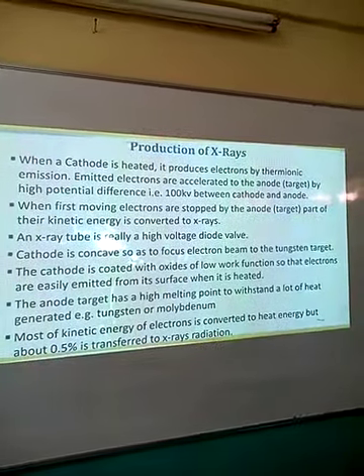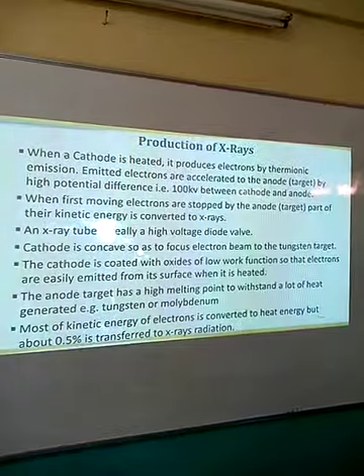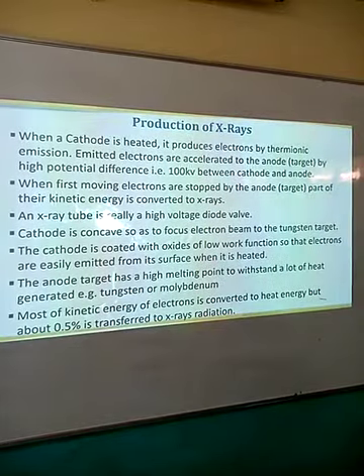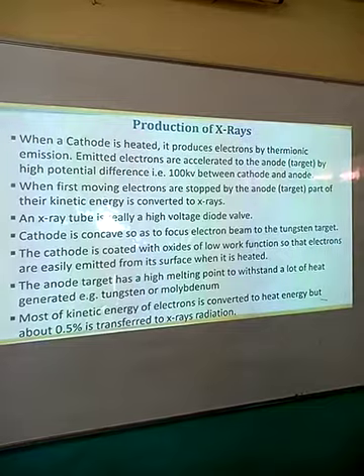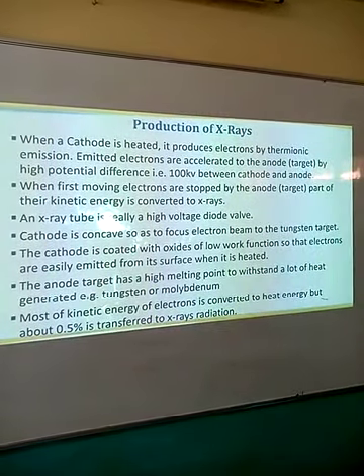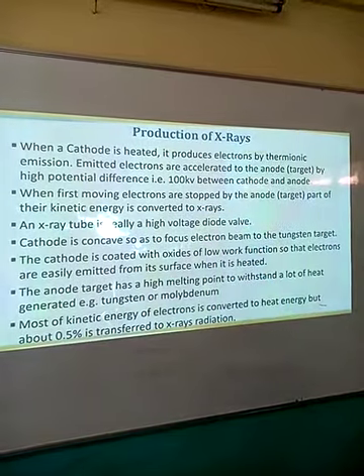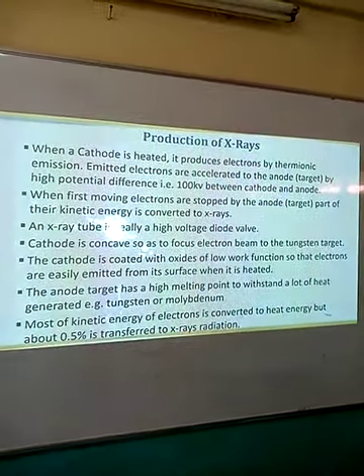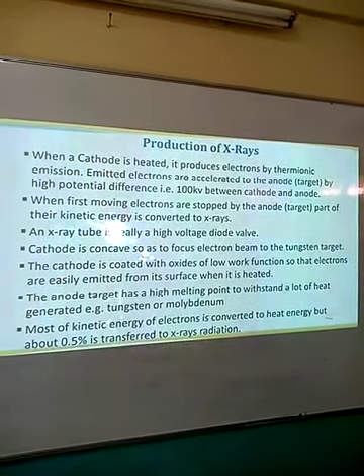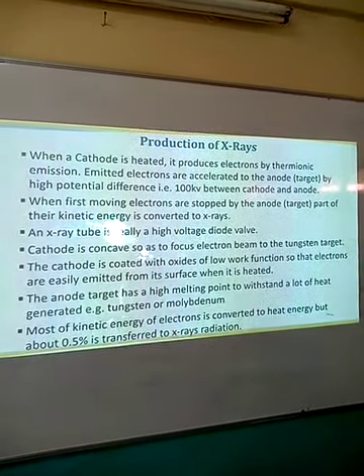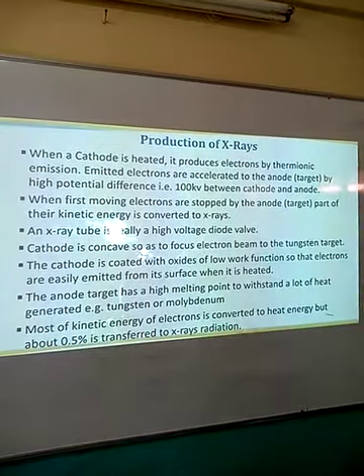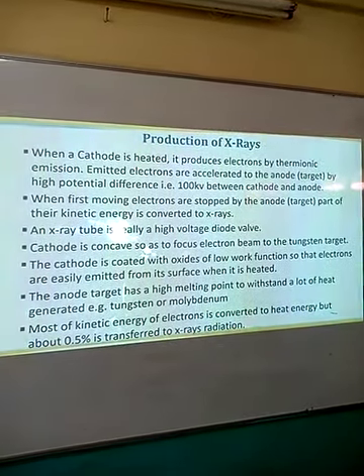Next, we have the production of X-rays. The first step involves the heating of the cathode. Once the cathode is heated, electrons are produced by the process of thermionic emission. The electrons are then accelerated towards the anode, which we call the target. The potential difference between the anode and the cathode is very high, always at 100 kilovolts. This potential difference is what accelerates the electrons to the target. The fast-moving electrons are stopped by the anode, which is the target. Once stopped, the kinetic energy of these electrons is converted into heat energy, and only 0.5% is converted to X-rays.